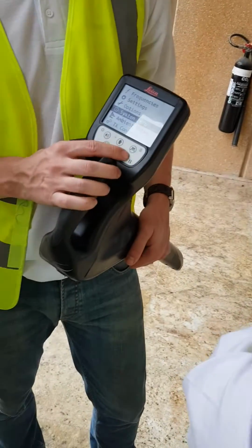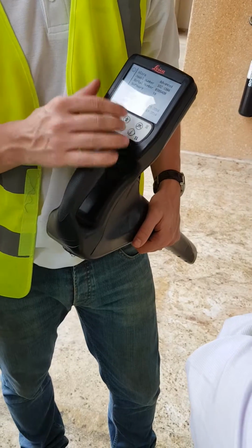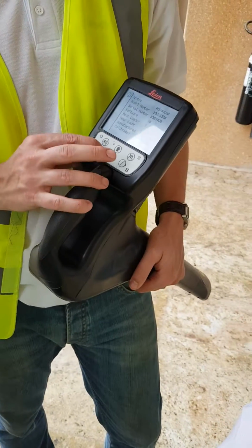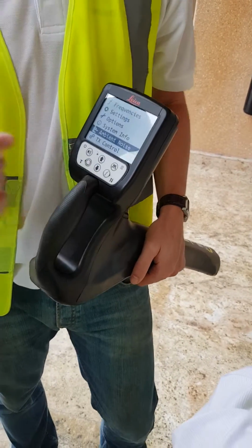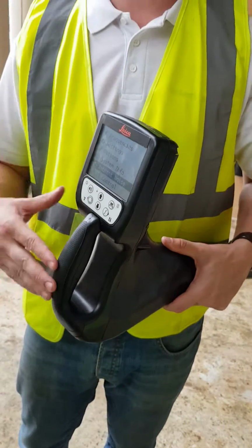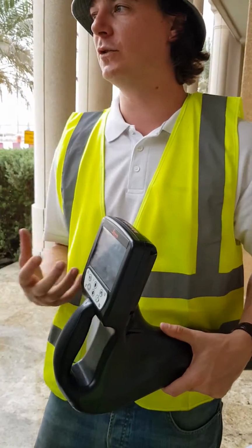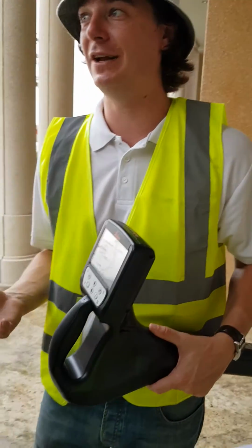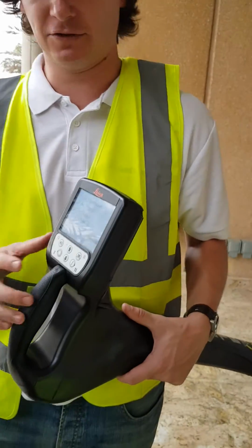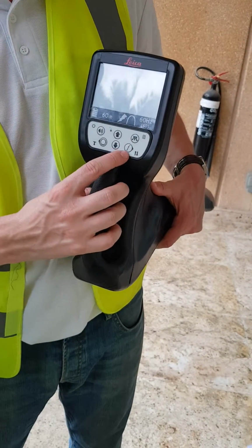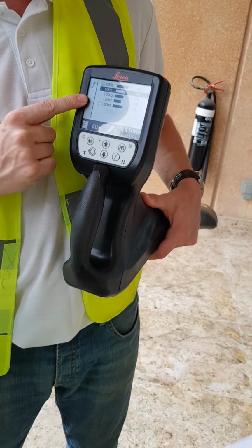System information is your firmware, all general information of the locator. Ambient noise is the one I mentioned, so this is one of the features on the advanced model. This means if you click on this one, it will tell you what frequencies are in the area, what would be a good signal to use on your transmitter, and what would be a really bad choice because it would have lots of interference. So all you do with this one is you click the arrow across, and straight away it will start to search.